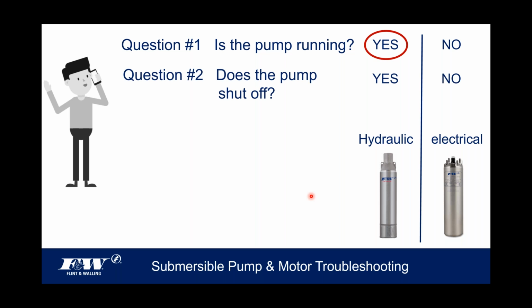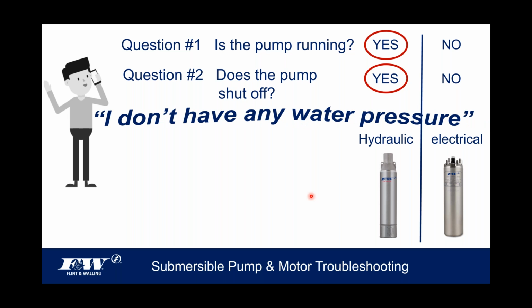So if they say that the pump is running, here comes my next question. Does the pump shut off? There's, again, two choices there, right? So if they say the pump is running and I ask them, does the pump shut off, and their response is yes, now let's stop and think about this just for a second. They called, they said they had very little water, they don't have any water. They tell me that the pump is running, and they tell me that the pump is shutting off, meaning it is building up at least enough pressure to satisfy the pressure switch and shut off. So when I look at that, I'm thinking, okay, the motor seems to be functioning fine, but obviously the pump's running and it's shutting off, and this customer still has an issue, right? They still have an issue.